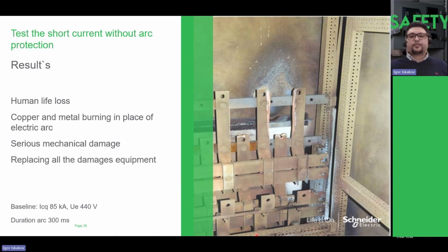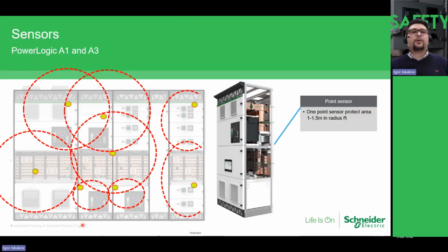When we have this arc flash duration of 300 milliseconds, you see it's almost completely burning, so you cannot use this switchgear. The voltage is 440 volts and the current is 85 kiloamperes, so you cannot use it. In case it's not fully covered, usually they're quite secure because the mirroring effect also activates your sensors.